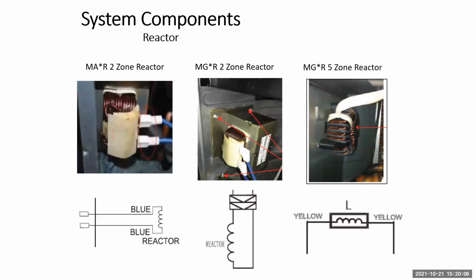And we're going to check our reactor. System's still off, so we're going to pull the wires off. We're going to check resistance, and we're looking for 1 ohm of resistance or less. If you have anything 1 ohm or higher, you need to replace that reactor. And don't forget to check it to ground. Always check everything to ground just to be certain.